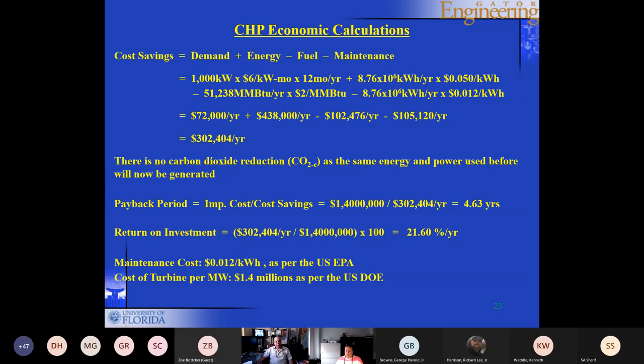You end up with about $302,000 of savings every year. There is no carbon dioxide reduction associated with this AR, because the same energy and power used before will now be generated. The payback period is implementation cost divided by the cost savings, return on investment as before. The maintenance cost has to be factored in, which is about 1.2 cents per kilowatt hour. This is the number the Environmental Protection Agency recommends. And again, the 1.4 million per 1 megawatt for the cost of the turbine.